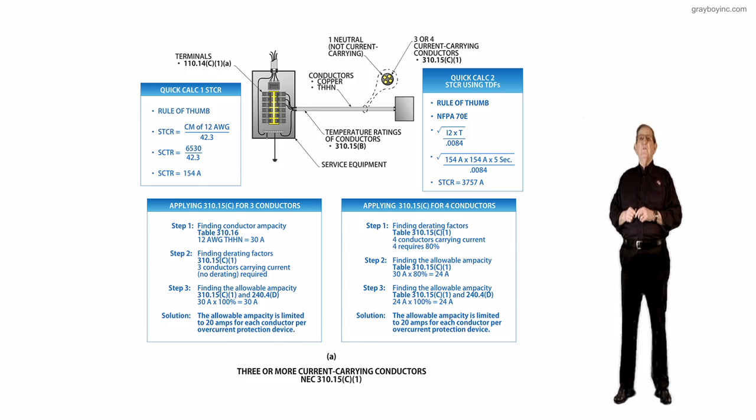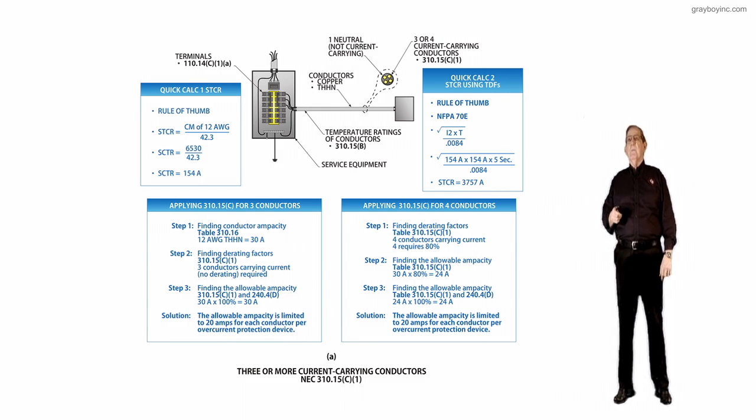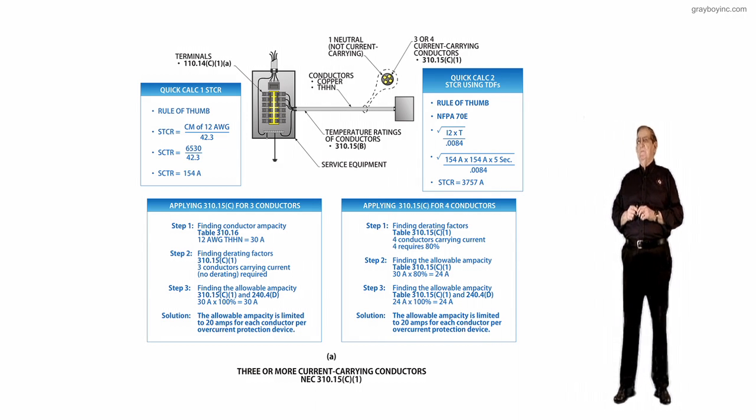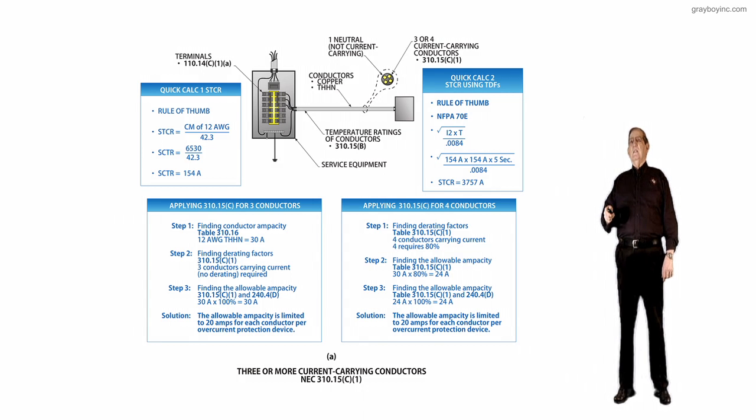Again, rule of thumb, if you actually calculated it, it could be different. Now let's look at quick calc 2 for the short-time current rating, but you're using time-delay fuses that will clear faster than 5 seconds. Then in NFPA 70E, you take current squared times clearing time, divided by 0.0084 seconds, and that's how fast a time-delay fuse will open.